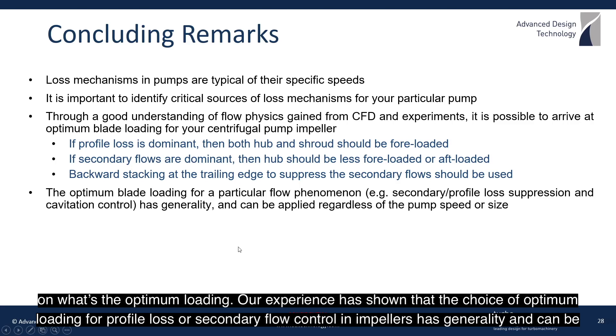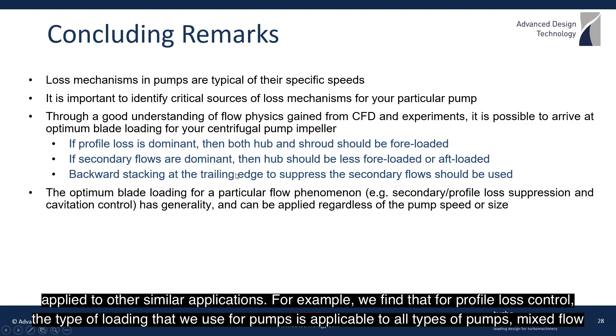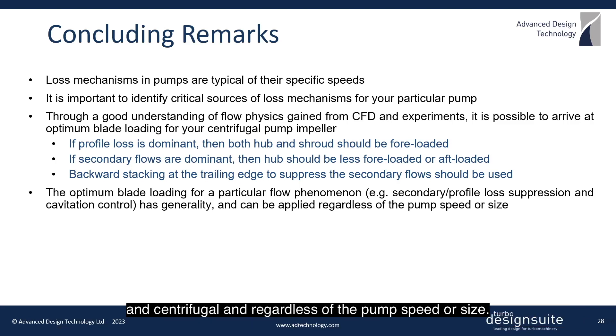Our experience has shown that the choice of optimum loading — whether for profile loss or secondary flow control — has generality and can be applied to other similar applications. For example, for profile loss control, the type of loading we use for pumps is applicable to all types of pumps, both mixed flow and centrifugal, regardless of pump speed or size.